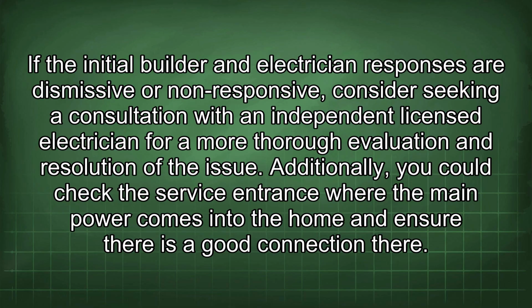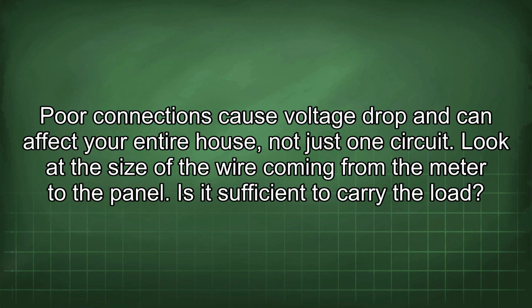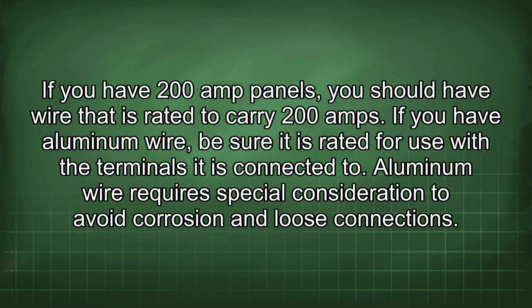Additionally, you could check the service entrance where the main power comes into the home and ensure there is a good connection there. Poor connections cause voltage drop and can affect your entire house, not just one circuit. Look at the size of the wire coming from the meter to the panel. Is it sufficient to carry the load? If you have 200 amp panels, you should have wire that is rated to carry 200 amps.